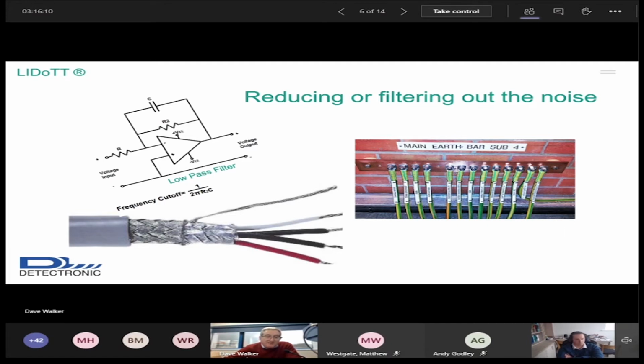Bottom left of that screen, we've got what's called a braided core, a screened core. So you've got your cables in there, and you've got this braided screen wrapped around that. Now, that's great. And what we have to do as electronic engineers is, as long as we put that screen to earth, that's going to create a Faraday cage around the core signal cables and protect them.